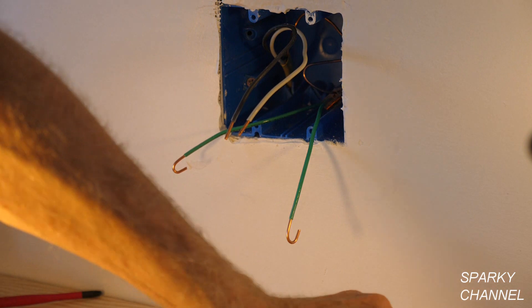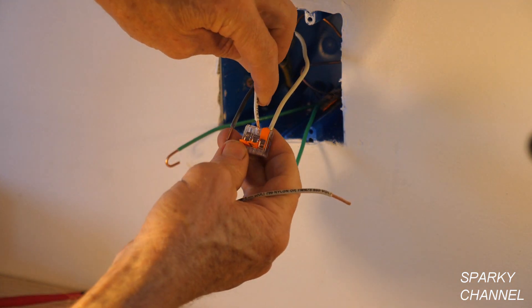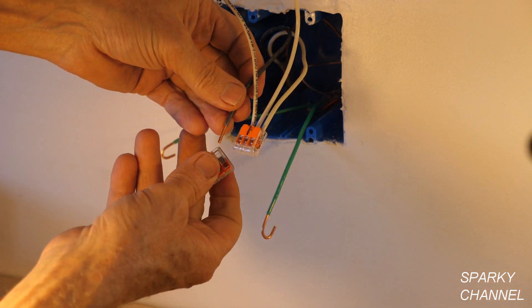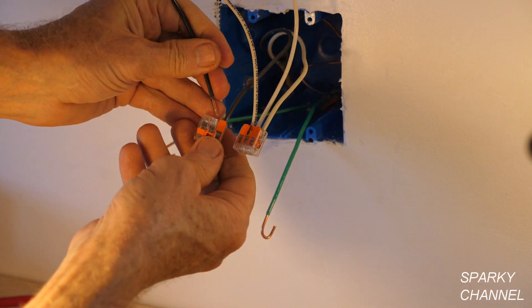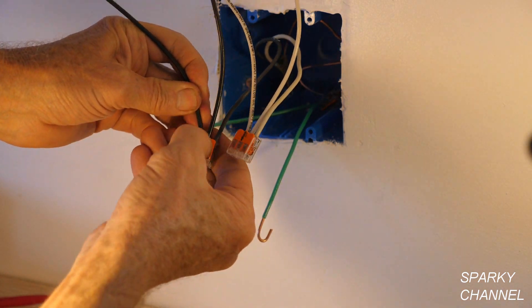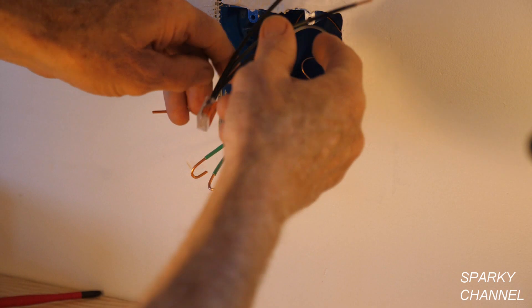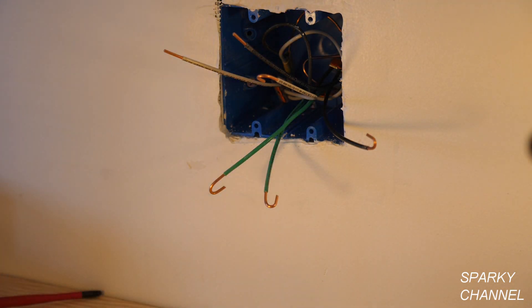For the neutral, I've got two pigtails ready — one for each outlet. Then for the hot wire, here is a three-connector Wago lever nut. You put it on, add the pigtails, push them all the way in, and click down. We're putting the neutrals and hot wires back into the back of the box — ground, ground, neutral, hot, neutral, hot — ready for the devices.